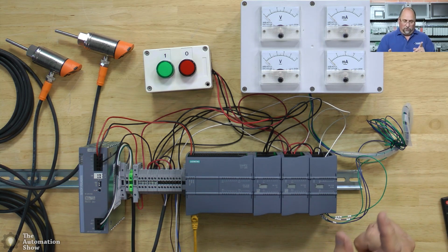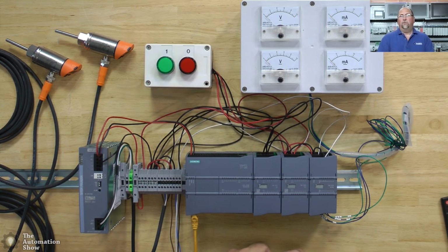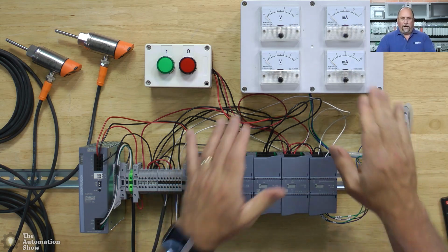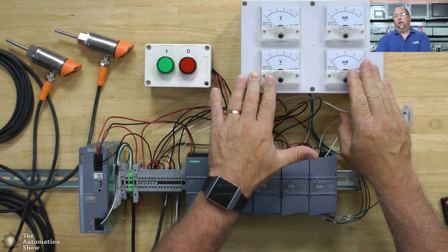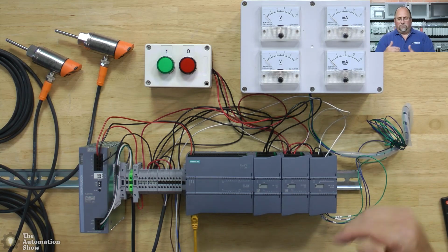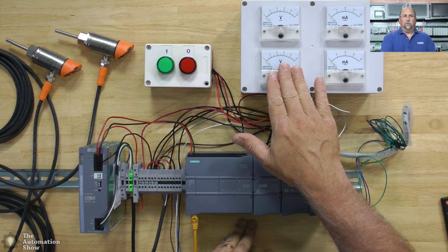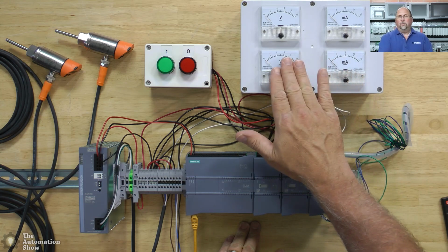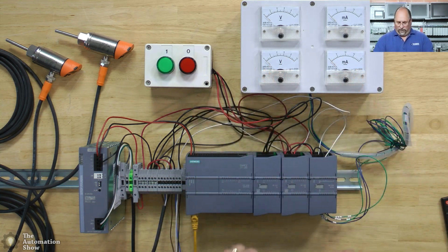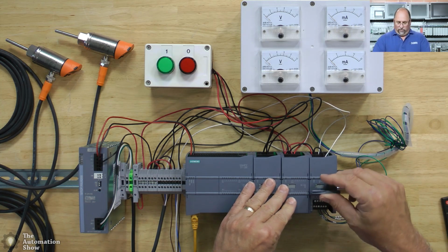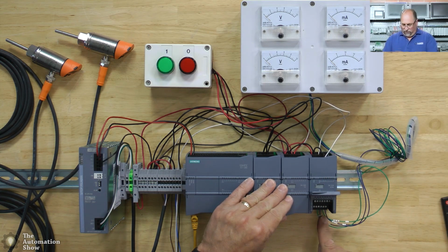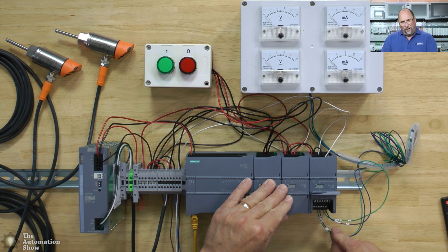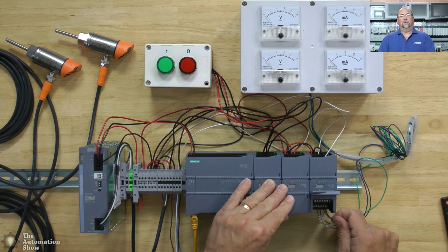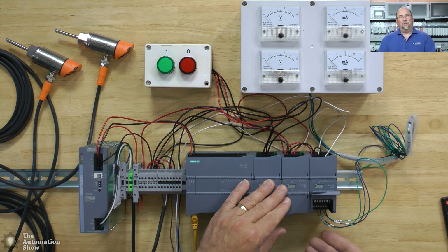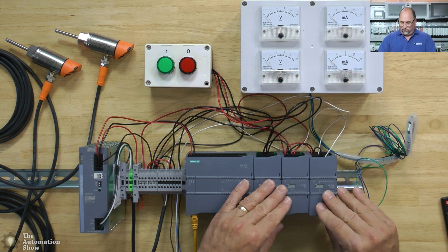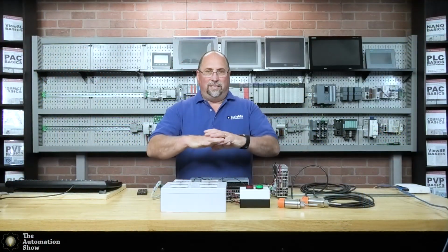Now for my outputs, digital outputs, I just wired in a couple of leftover LED pilot lights from one of my courses, as well as the meters I use when I'm teaching analog, you know, getting started with analog modules. So I have 0 to 10 and 4 to 20 meters right here. So we'll be using these two right here. So those are wired, you can see right here on the analog output. You can see I have the first one, output number 0, wired as current, and the second one is wired as voltage. The wiring here looks identical, right? But these meters are actually different inside. So with that said, that's the whole setup here.